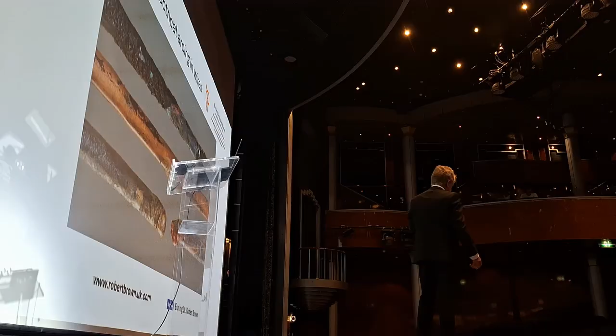As a forensic engineer, when I go and look at forensic evidence, let's say in the case of an electrical fire, I look at electrical conductors. This is an example of a copper conductor, well, three copper conductors, in various stages of their disintegration. So this top conductor has a copper core, and on the outer edges here, it would be covered in a plastic coating insulator.